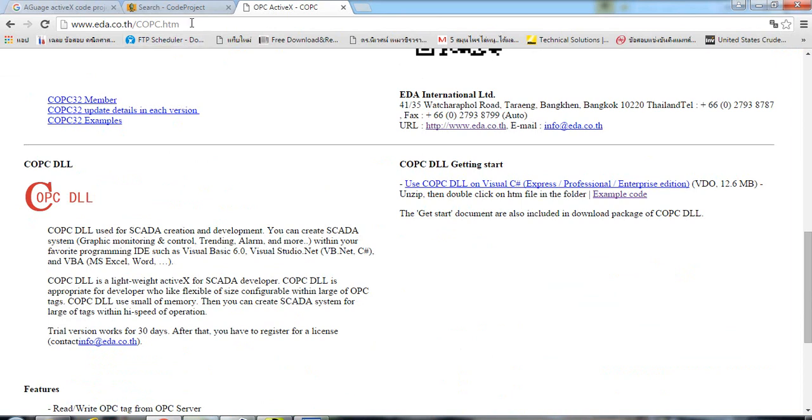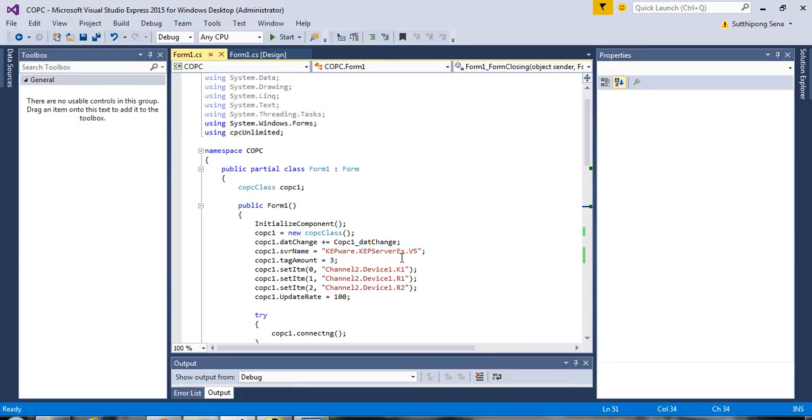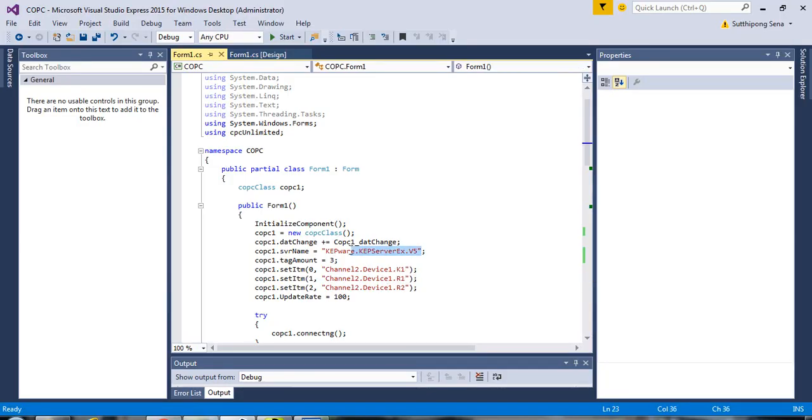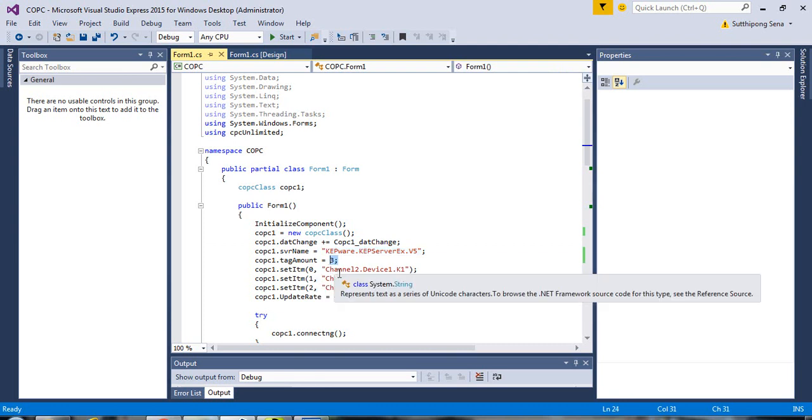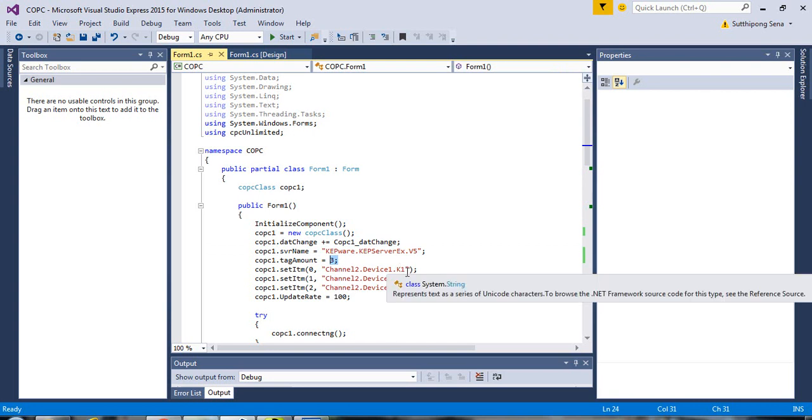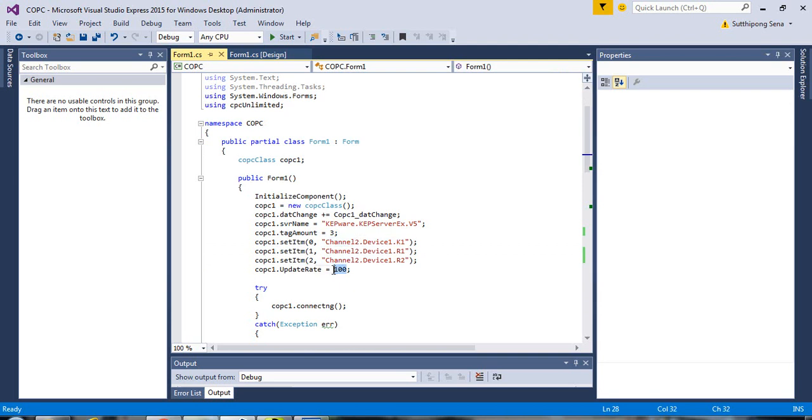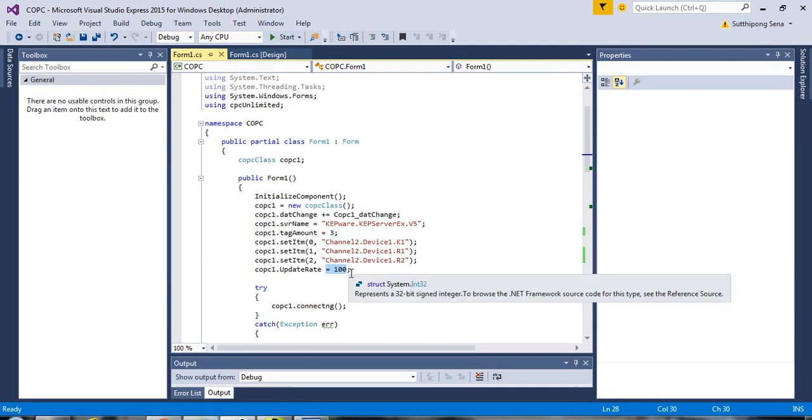I have put the link in the video description, and this is the simple code. Specify the OPC server name. Specify the amount of tags and the OPC tag names that you would like to connect, and the update rate. In this case, it is 100 milliseconds.